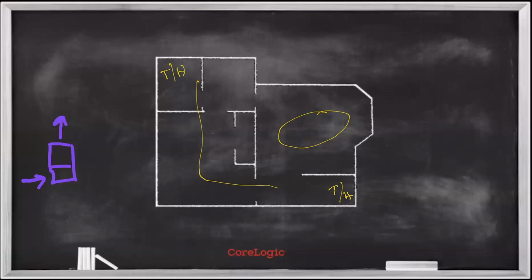That right-hand side is not an intake. That right-hand side is the hubcap of the motor, right? There's a tiny bit of air that goes in there, but that air is just cooling the motor down. 90% of your air is coming in that left-hand side. But 90% of your air is coming in on the left-hand side.